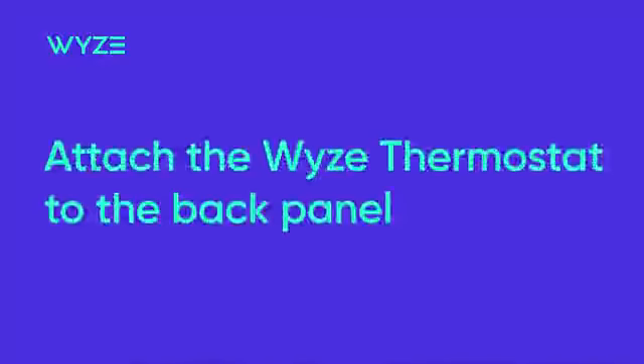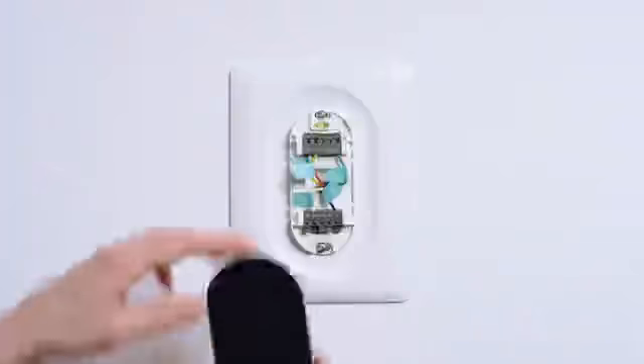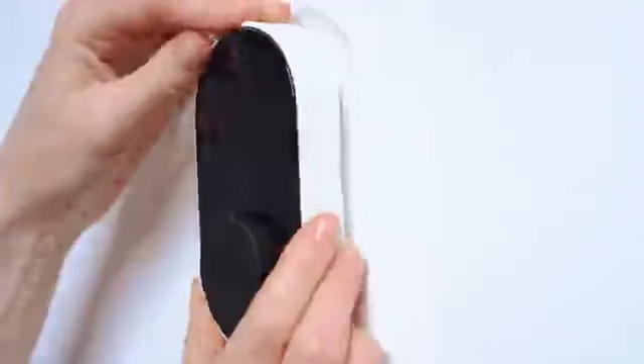To connect the wires to the back panel, push the lever down and insert the wire to the hole nearest the center. Do not put the wire in the outward-facing hole. When a wire has been fully connected, the lever will stay down. Gently press the Wyze Thermostat onto the back panel. You will hear a click once the display is securely on the base.